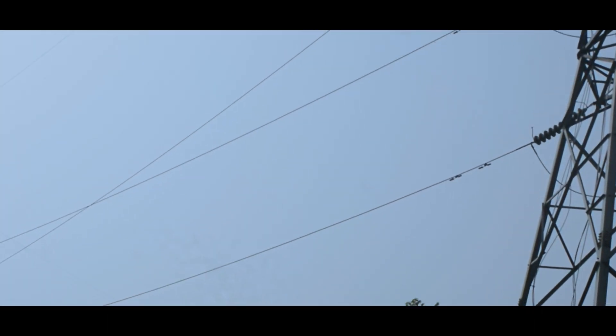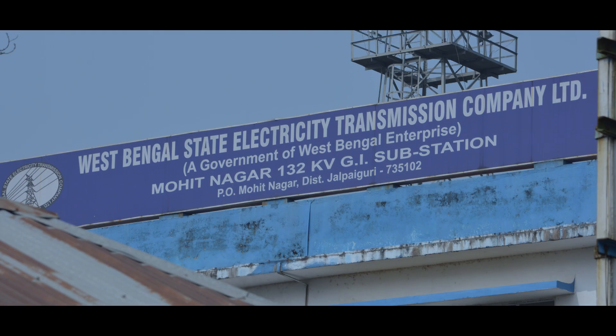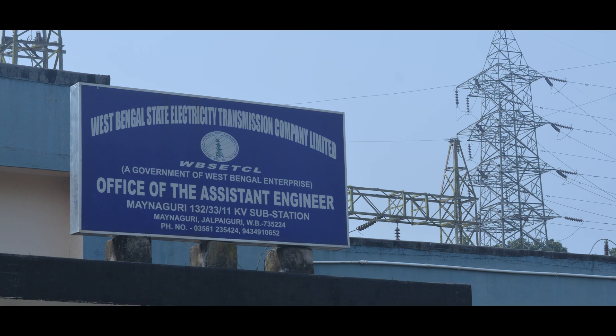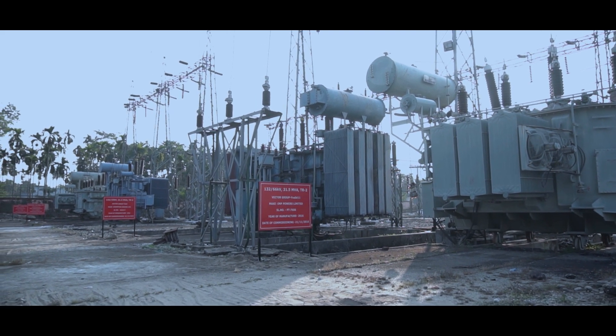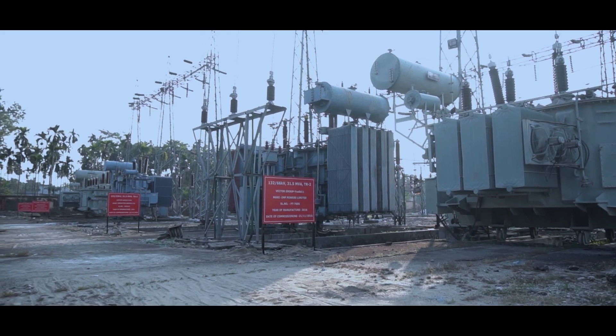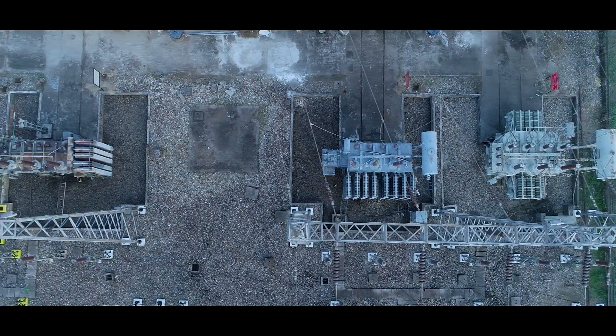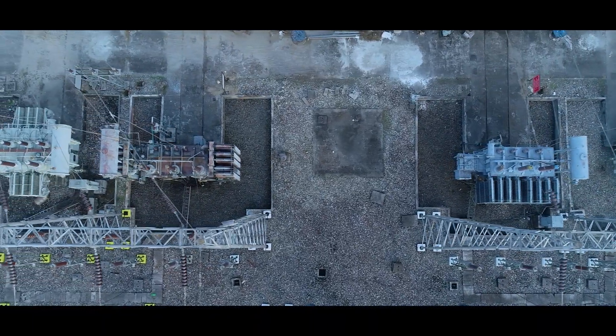At present, Chalsa 132kV substation is connected to the grid via 132kV lines from Mohitnagar 132kV GIS and Maynaguri 132kV substations respectively. The installed transformation capacity at the substation is 63 MVA each at 132/33kV and 132/66kV, while the capacity at 33/11kV level is 26.3 MVA.